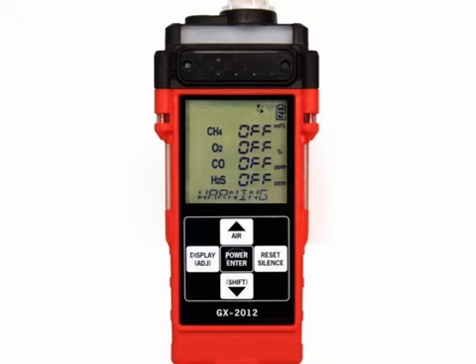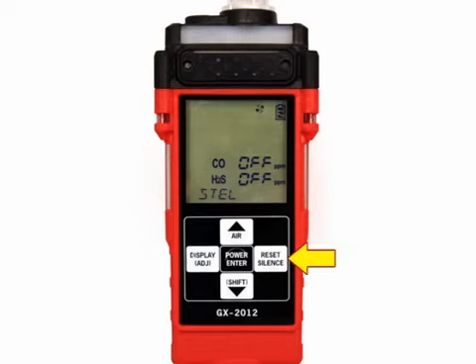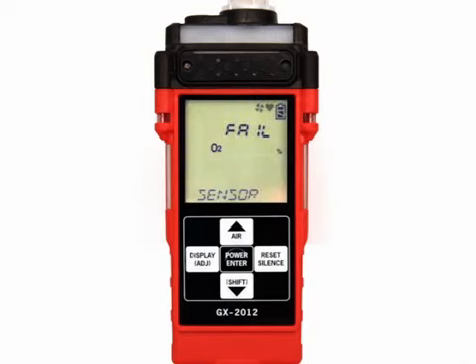If the HC range is set to % volume only, you will have to press and release the reset silence button for each of the previous screens to acknowledge that there are no alarms when the unit is operated in that fashion. If the GX-2012 experiences a sensor failure during startup, a screen will display indicating which sensor has failed. If you wish to continue, press and release the Reset Silence button to acknowledge the failure. The instrument will then proceed to normal operating mode. Once in normal operating mode, the gas reading for the failed sensor will be replaced by 3 dashes. The failed sensor should be replaced as soon as possible.